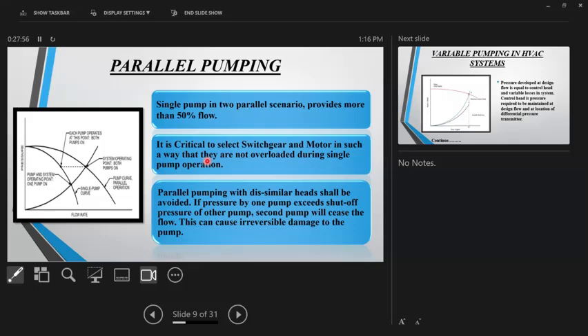Yes, I have a question on this best efficiency point, BEP. For the selection software, is the BEP identified by itself, or should we consider anything? No, the best efficiency point is actually set by the manufacturer, that you and I won't know. For a given pump, given impeller dimensions, and given volute size, one RPM curve will have one best efficiency point. If you see the pump selection curves, they identify the BEP, the best efficiency point.